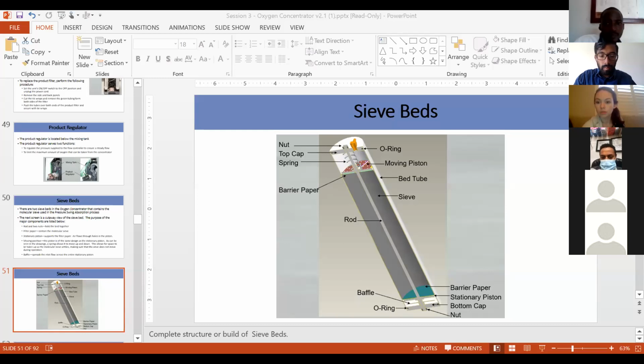You don't have to compress, because the system itself has that particular pressuring mechanism. If you see, there's an O-ring and a moving piston with a spring. That particular spring is going to give the pressure inside the sieve bed. So that's how it works. You do not need to apply any compression pressure on the sieve bed.